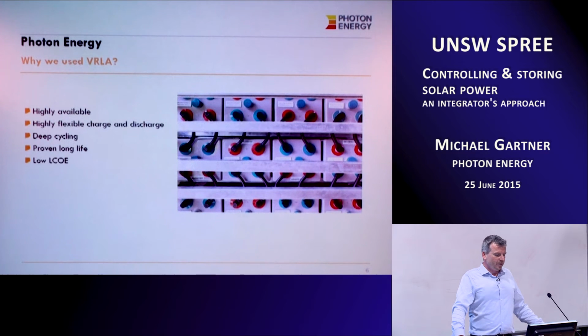When we looked at the type of load used at that site, it's a relatively constant load. For that sort of load, lead-acid batteries actually seem to be quite good. They have relatively flexible charge and discharge rates, which is very important because when storing energy from solar, we generally have a lot of power available during midday, so our charge rate is very quick, whereas the discharge rate is quite slow. This additional flexibility is quite useful in VRLA batteries. They can carry an incredible amount of current - it's actually amazing what they can do. So from that perspective, it was a very good choice.